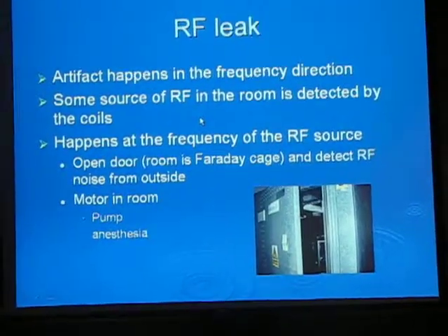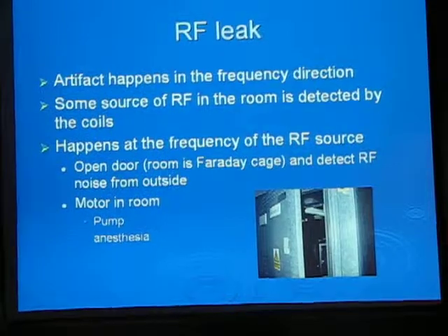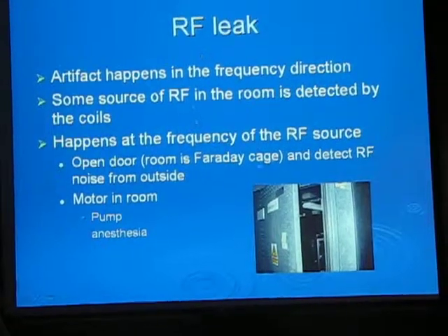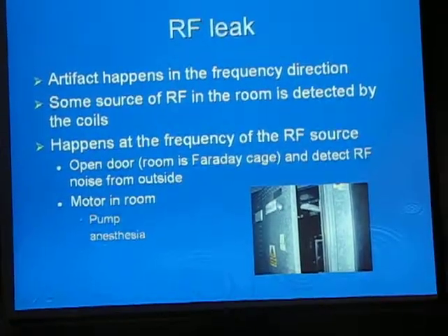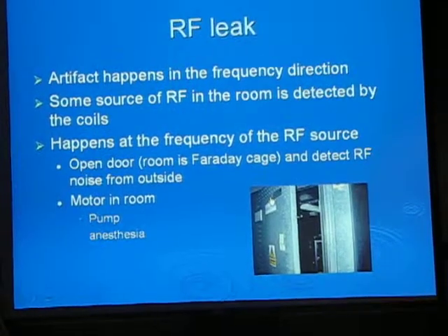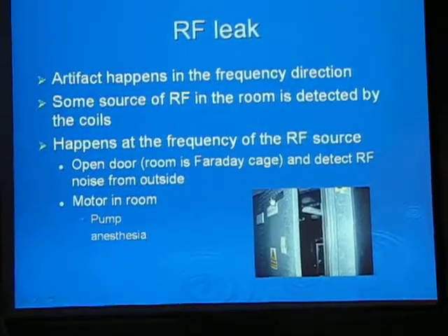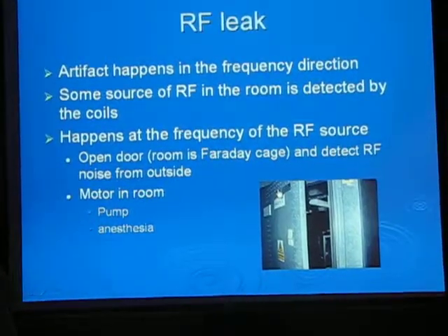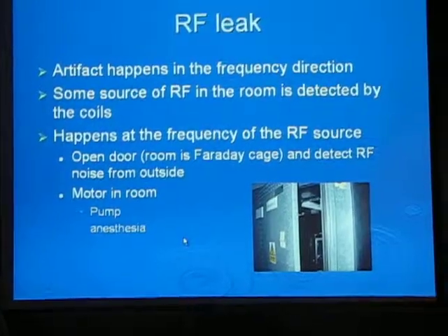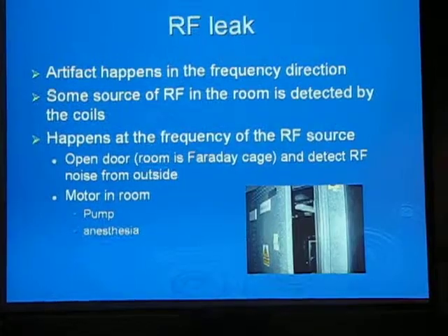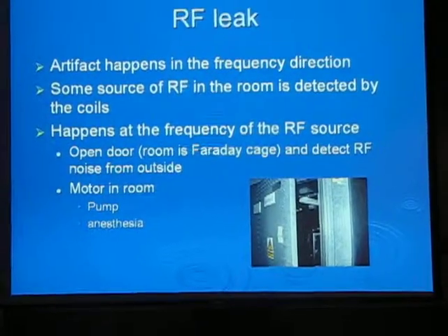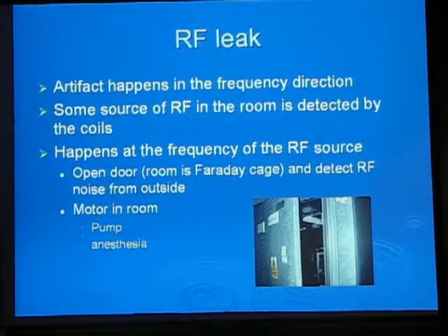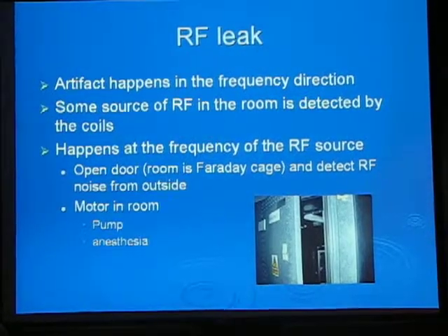So the MR rooms, you'll notice, if you look at the door, there's sort of this copper lining on the door, and it's actually around the whole room. It's called a Faraday cage, and so you have a conductive door. So what is the purpose of that conductive lining, that conductive encasement of your MRI unit, of the whole room itself? So related to that question, why do we surround the room in copper? Go ahead.